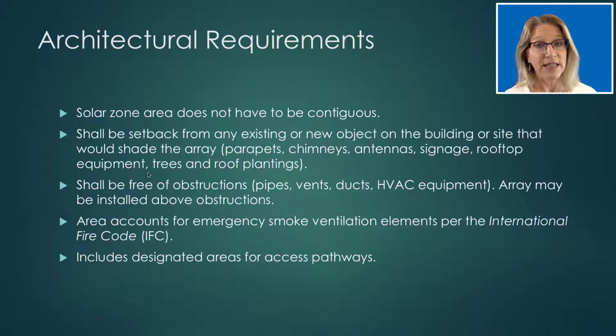However, the plan could be that the array may be installed above these obstructions. If that's the case, what the code says is that if the designated area is over these obstructions, then the structure that would be necessary to support the array does need to be included in the original first construction. So that would not be something that could be added later on. And then the area does need to account for any emergency smoke ventilation elements of the fire code. And the architect also needs to designate areas for access pathways from a roof access point to the arrays and the inverters so that they can be maintained.